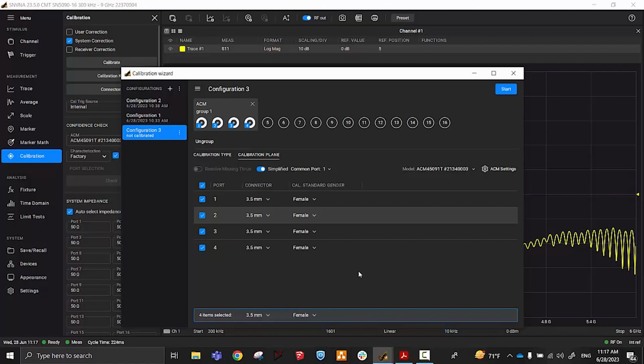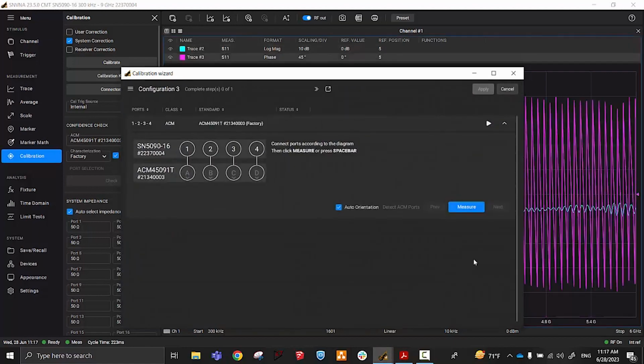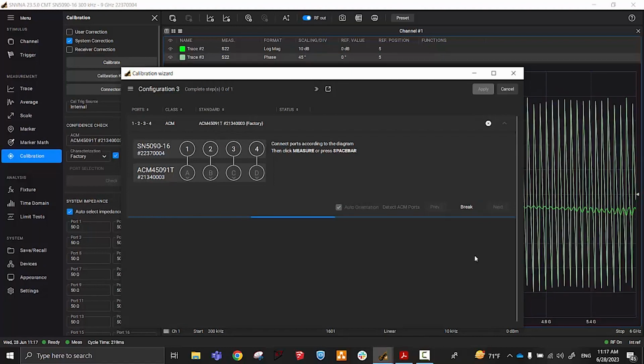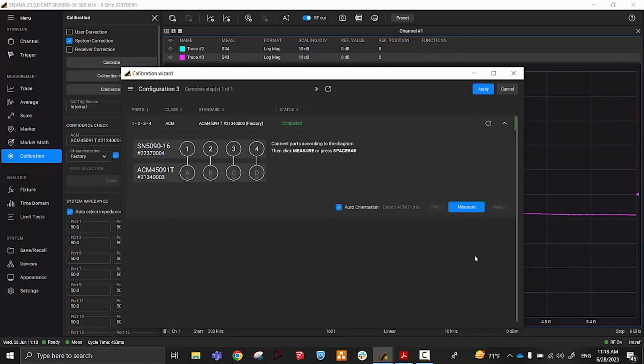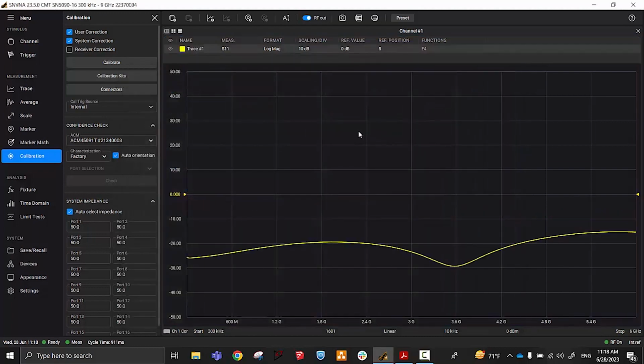And, yeah, actually, I should be a little more clear. It's the Cal standard gender that we're talking about here. So the ACM has female connectors. So let's go ahead and start that automatic calibration. And it will go through the first 4 ports. All right, we'll apply that calibration. So now we have a 4-port calibration completed for these first 4 cables, ports 1, 2, 3, and 4.